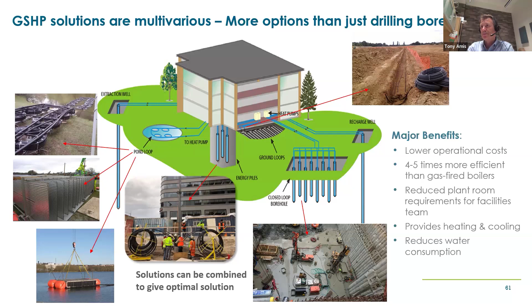So you can see now that if the foundations are deep enough, energy foundations have a significant benefit in terms of low operational costs and lower install costs. And we've already said heat pumps are 4 to 5 times more energy efficient than gas-fired boilers. These units will provide heating and cooling too, so you can save room in a plant room. Ultimately, a lot of cooling we see is done by evaporating water on a roof - a pretty important resource just being evaporated into the atmosphere, adding to global warming, and using what will become, I believe, a very valuable resource over time.